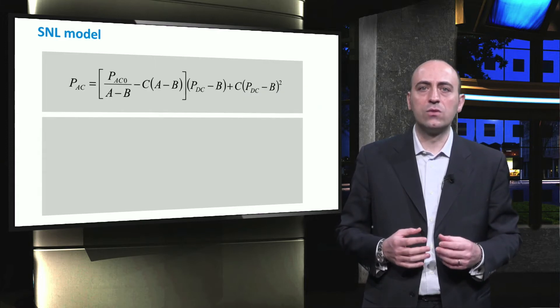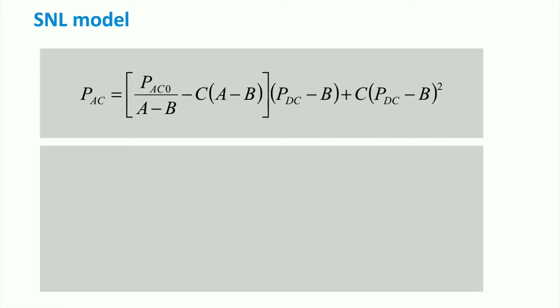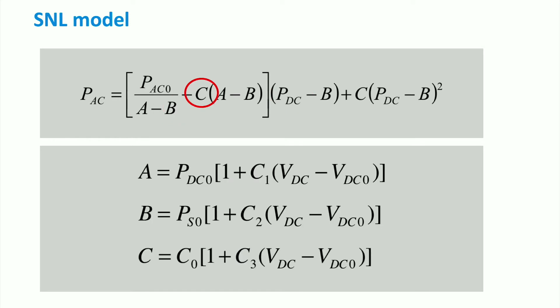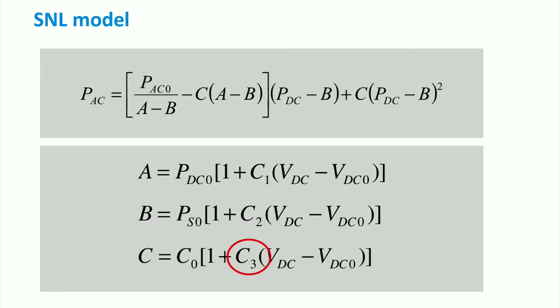The SNL model also provides empirical formulas for the AC power output as a function of different parameters, most of them already described in the previous slides. PAC0 is the nominal AC power of the inverter. PDC is the instantaneous DC power provided by the PV array. Some other empirical parameters are used: A, B, and C, all shown on the screen. In these three parameters, we can find some coefficients already seen before, such as PDC0, which is the nominal DC power input; PS0, which is the inverter self-consumption; VDC, which is the PV array side voltage; and VDC0, which is the nominal DC voltage value. The last parameters always provided by manufacturers are C0, which takes into account the curvature of the characteristic, and C1, C2, and C3, which are purely empirical parameters.